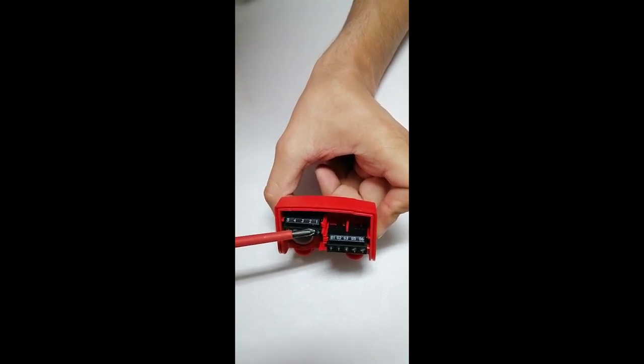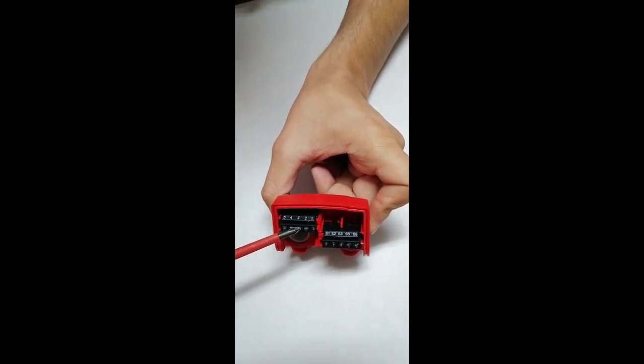These are the connections for the switches, and these are the connections for the 0 to 10 volt control signal, the feedback signal, and the 24 volt power supply. The 24 volt power supply is on number 1 and 2. Number 3 is the control signal from the DDC controller, and number 5 is our feedback to the controller.